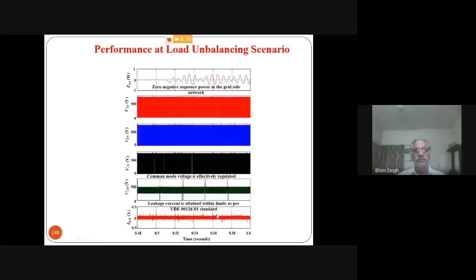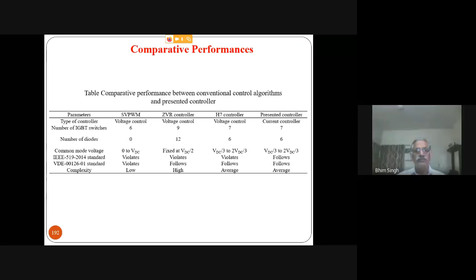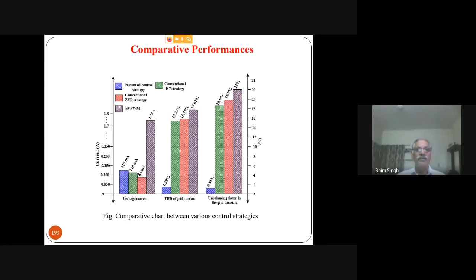Typically the system limit is per the VDE standard, which says not more than 300 milliampere current should be there for the leakage current. Otherwise it's supposed to be more in that case, like in a 6-level inverter. So all those aspects our student took up, covering all those features.